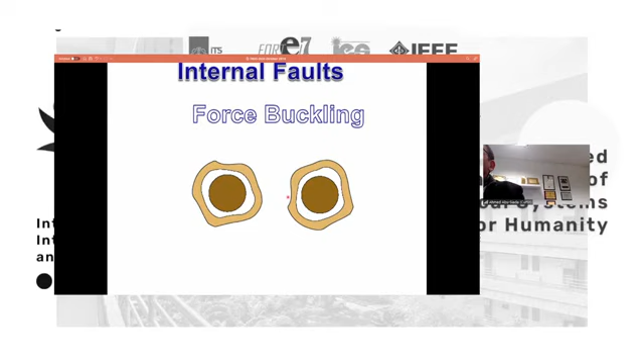Leakage fault is coming from the oil. Look what will happen here if you lose the dielectric ability of the oil: you may have some leakage current coming from the winding to the tank outside. Axial displacement: when you have huge electromagnetic force on one winding, you have two components, one upward and one downward. If they are not equal, you may have a movement like that. Buckling, forced buckling: again, the electromagnetic force could be in the radial direction, causing buckling like that. And you have seen that in the first 2 or 3 slides. Or radial deformation, when your internal winding here will move inward to the core, causing core deformation.